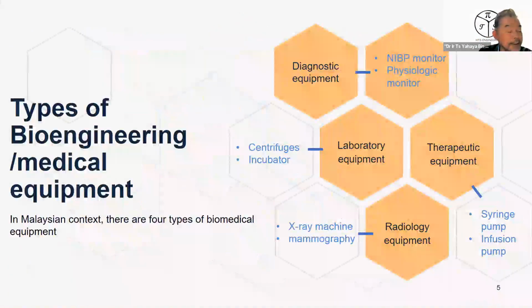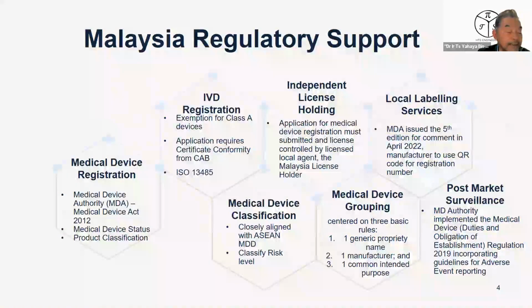Under this, the mandatory problem reporting is part of post-marketing risk assessment. It is there to measure the continued safe use of medical devices, and is an important part of the post-market surveillance system. The mandatory problem reporting is also referred to as adverse event reporting in the ASEAN Medical Device Directive, AMDD, and the objective is basically to improve the protection of the health and safety of patients. Under this act, it is mandatory to report to the authority when an incident involving a medical device has occurred, and this report is to determine the root cause of the incident and the corrective and preventive action to eliminate or reduce the risk.